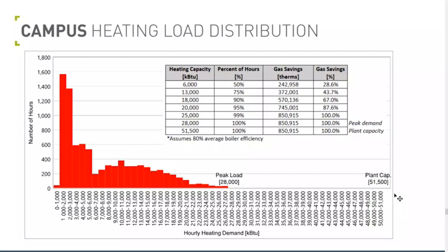Okay, got it. When we energy model and actually take into account diversities, load factors, and different things going on in these buildings, we know we're probably only going to be, sometimes up to here, but usually 50 to 70% of that peak load calculated by the mechanical engineer. That's okay - they need to be able to handle the worst condition, the worst day. Otherwise there are other things going on. You're not going to have a happy owner when that one hour happens out of the entire year.